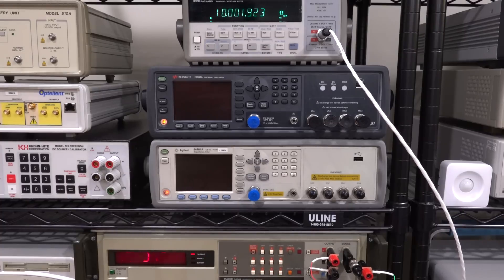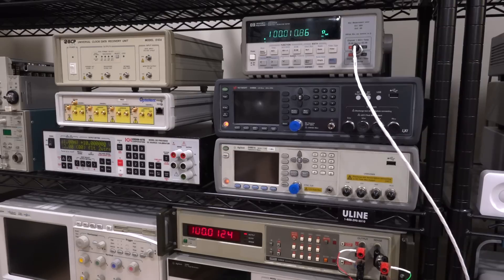Really happy with this. Clearly this instrument has maintained really good calibration. Typically these HPs maintain very good performance even over very long periods of time. Here's the result for 100 ohms - 100.011 versus 100.012. Yeah, I'm pretty happy with this. Looks good. There you have it. I hope you enjoyed this quick repair. I have a lot of stuff to get through. Sorry if this seems rushed, but I think it's more interesting to go through all the repairs that are waiting. See you in the comment section.